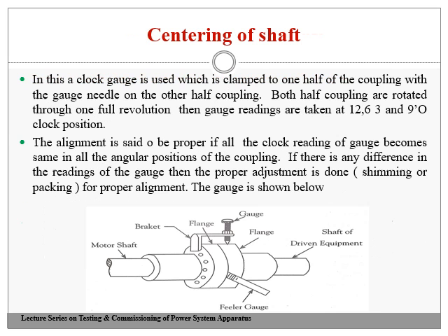Let us go for how to do the centering now. This is done with a clock gauge. In this, the clock gauge is used, which is clamped on one half of the coupling, with the gauge needle on the other half coupling. Both half couplings are rotated through a full revolution. Then gauge readings are taken at 12 o'clock, 6 o'clock, 3 o'clock and 9 o'clock positions.